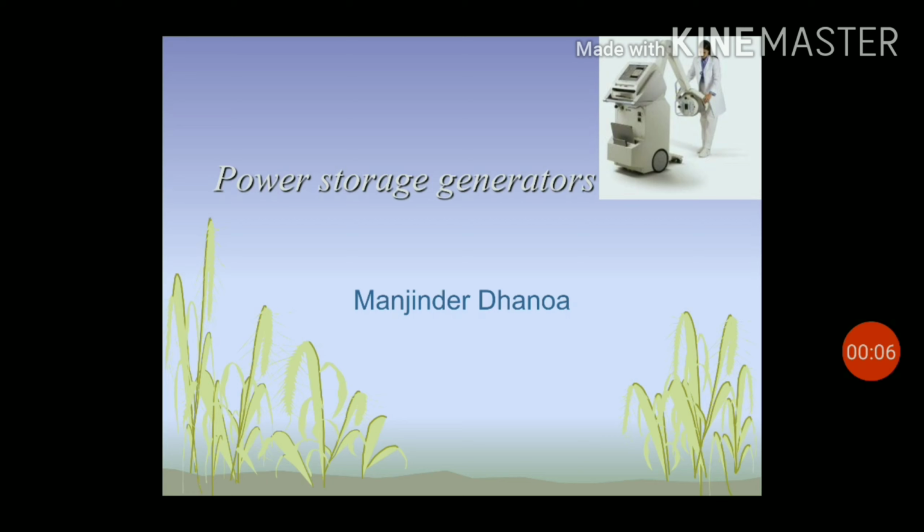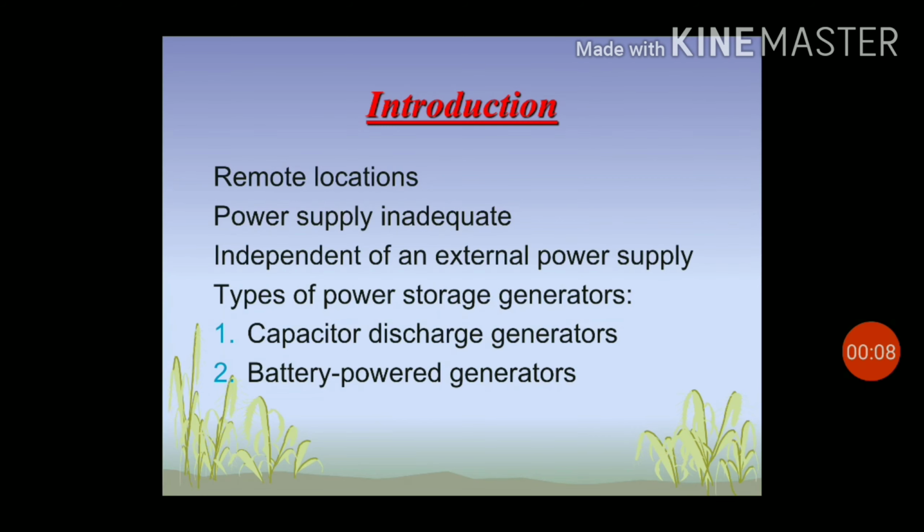Power storage units. Today's lecture is on the power storage generators used in radiology. When the patient is not able to come to the X-ray room, the mobile radiographic equipment is taken to the patient's room, where the power supply is not adequately available.